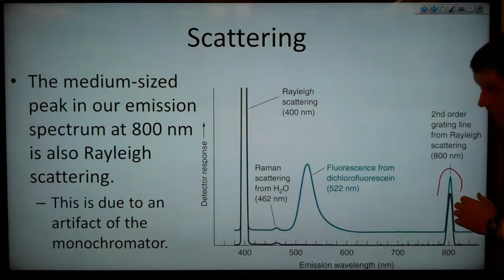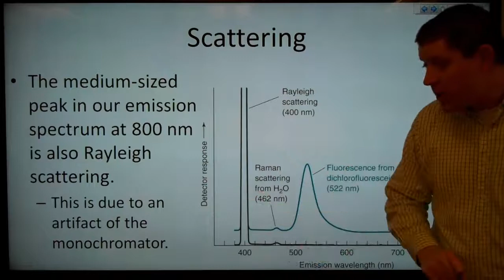The medium-sized peak in our emission spectrum over here at 800 nanometers, that's this one, is also from Rayleigh scattering. But this is due to an artifact of our monochromator. So a grating monochromator that passes a wavelength lambda will also pass light with integer fractions of the selected wavelength. So at lambda over 2, lambda over 3, lambda over 4, and so on. And note that each subsequent wavelength, so second order, third order, fourth order, and so on, passes the monochromator with lower and lower efficiency. So we're mostly concerned here with this second order one, the lambda over 2.